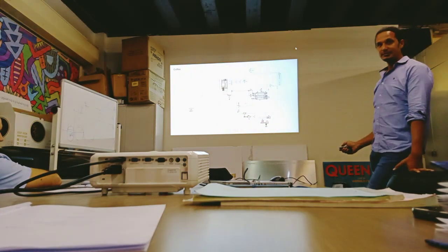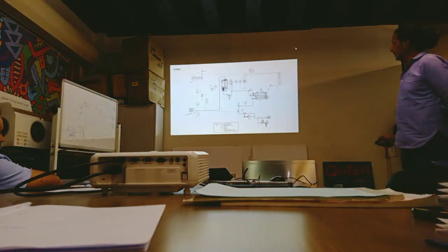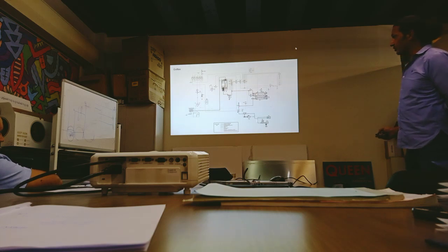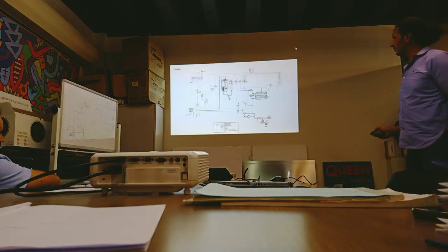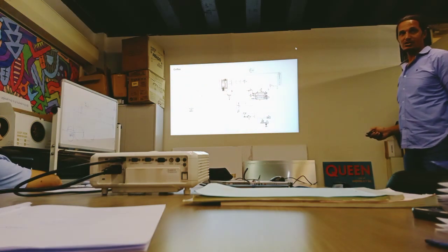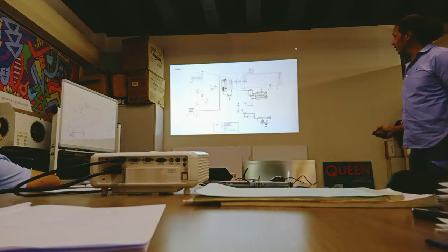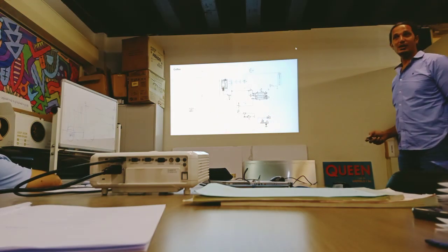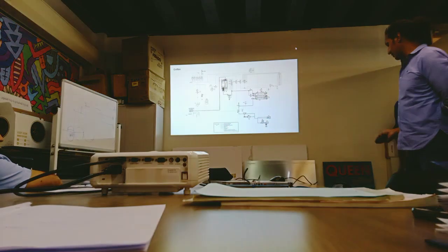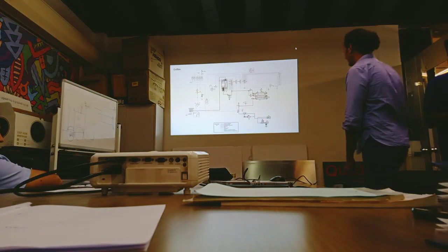Then what is this? VR. VR is the check valve, which doesn't allow water to go back to the pump. It allows water to go only in one direction. Then after the check valve, there is the VE. What's the VE? It's the expansion valve. The expansion valve, this one also you cannot clean or adjust.